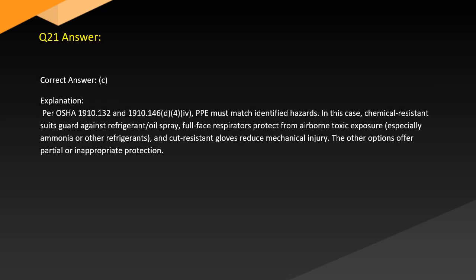Answer. Correct answer, C. Explanation. Per OSHA 1910.132 and 1910.146(d), PPE must match identified hazards. In this case, chemical-resistant suits guard against refrigerant oil spray, full-face respirators protect from airborne toxic exposure, especially ammonia or other refrigerants, and cut-resistant gloves reduce mechanical injury. The other options offer partial, inappropriate protection.